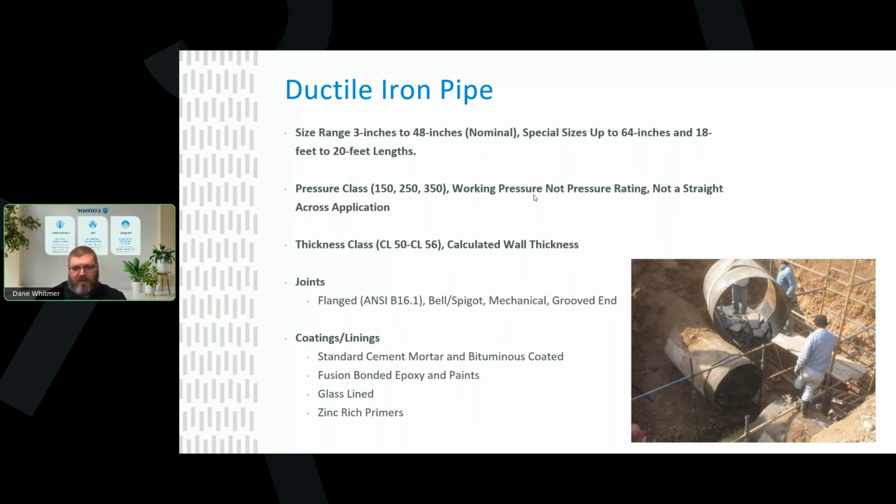And it turns out that the liner, the cement lining, had failed, and all those chunks had settled and got moved to the bottom of the hydraulic elevation of the pipeline system. That was probably more of a manufacturer issue than something that would really occur, but it can go to show that cement, ductile iron and wastewater is probably not your first choice, but it works really well and is a lot of the industry standard for water distribution.